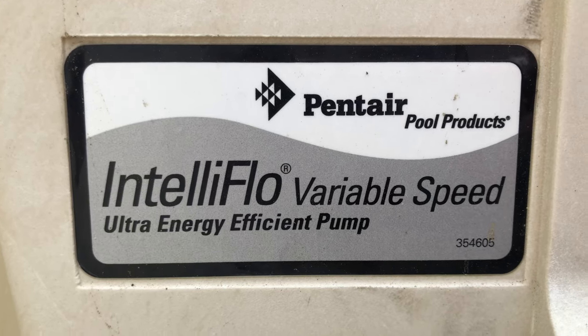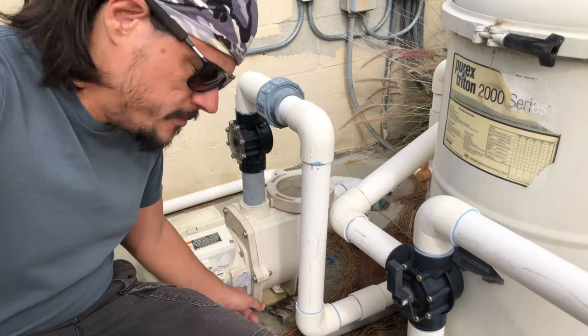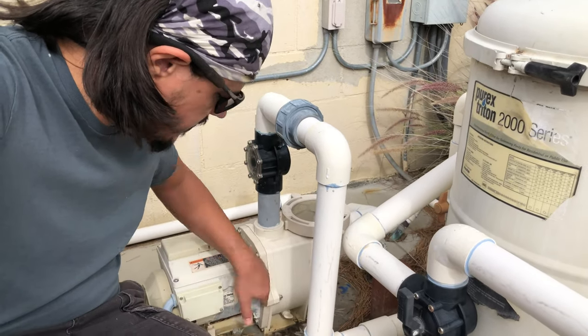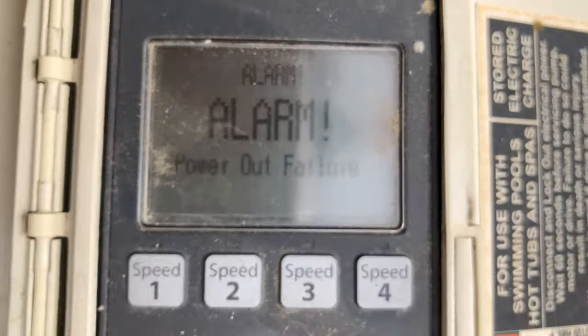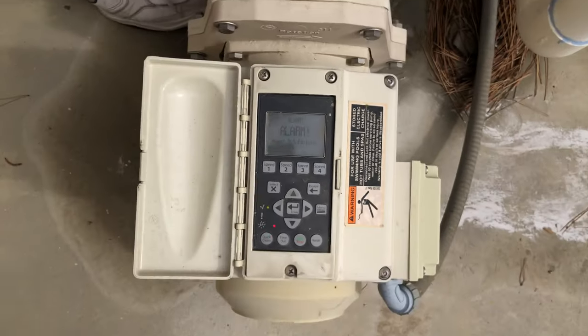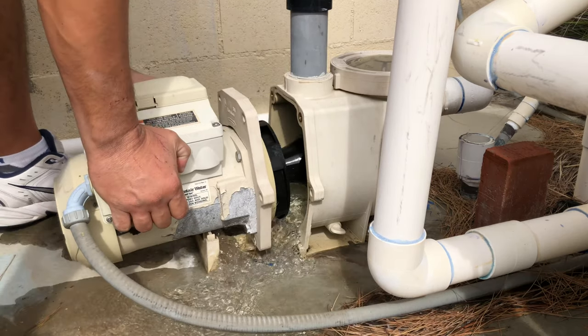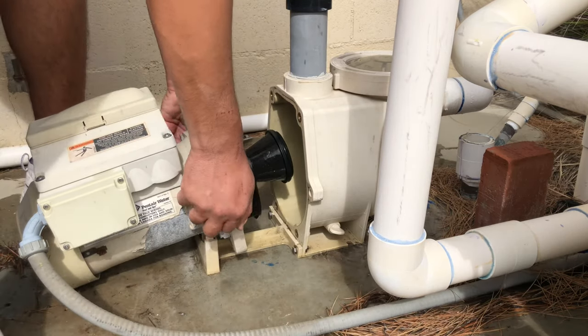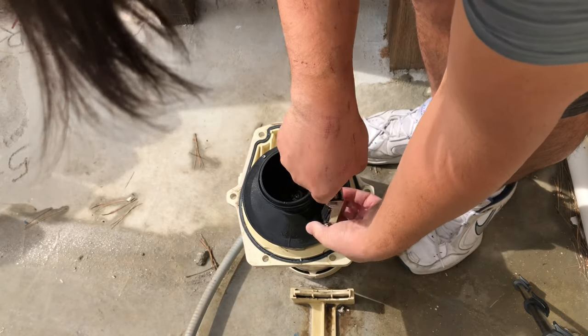We're installing the seal in a Pentair IntelliFlo variable speed pool pump. This thing is leaking at the pump seal, so we have to separate it in half and pull the impeller off. First, we're going to shut off the breaker — the pump is now powered off. Next, we'll remove the six bolts that hold the pump together and separate the pump. Turning the pump up on its back, grab an allen wrench to loosen and remove the pump diffuser.